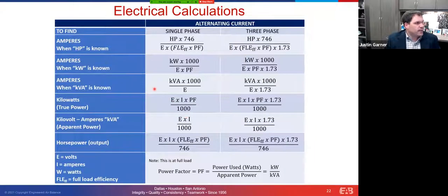All right, so let's get into electrical calculations here. I'm going to breeze through this because I'm running a little long at the moment, but this slide gives you some of the common formulas that you need to know when we start talking about amps, volts, and power, okay? And when we talk about power here in the United States, we typically refer to horsepower. 746 watts equals one horsepower. So just be aware of that. I'm not going to go through each one of these in great detail, but oftentimes folks think in the commercial world, well, I just multiply volts times amps and I get power. Well, that's true in a single phase system, but it's not true in a three phase system. You need to make sure that you're accounting for the three phases, or the square root of three, which ends up being 1.73. And so you've got to make sure you add that in when you're doing that basic calculation. We're going to go a little bit more in detail into this in the next few slides.